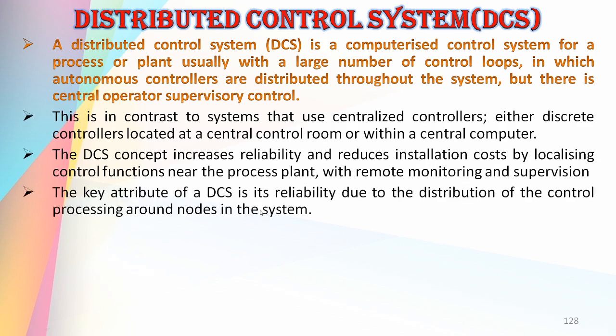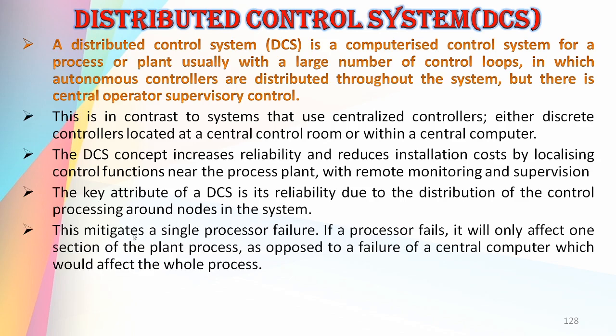The key attribute of a DCS is its reliability, due to the distribution of the control processing around nodes in the system, and this mitigates a single processor failure. If a processor fails, it will only affect one section of the plant process, as opposed to a failure of a central computer which would affect the whole process.